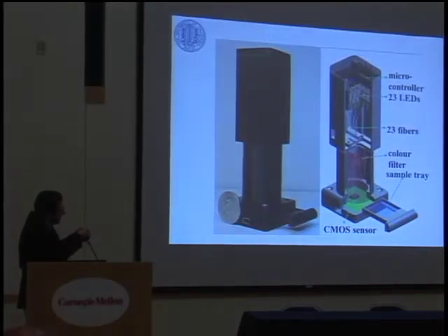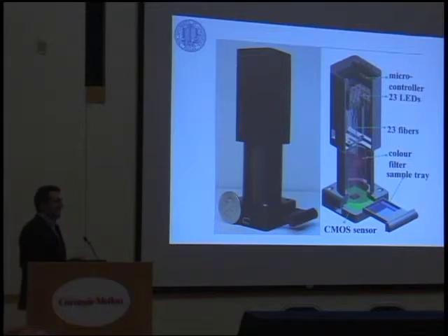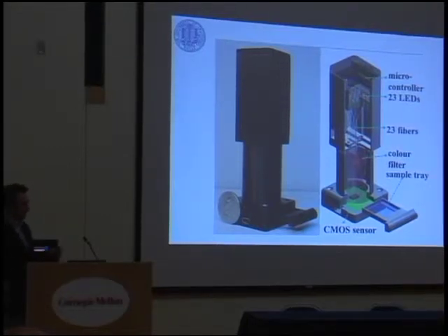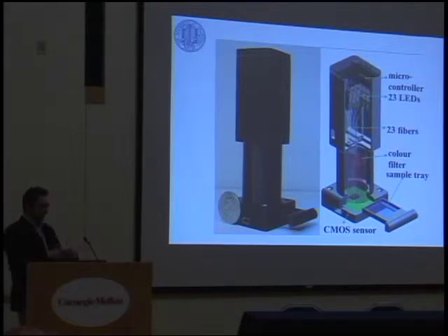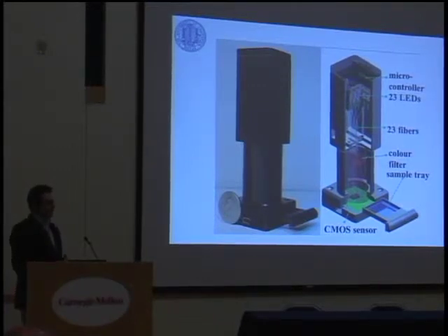The distance between the tip of this fiber and the sample is on the order of a couple of centimeters, let's say 4 centimeters. The distance between the sample and the active area of the CMOS is a millimeter range. That 400-fold reduction in the magnification means that if I move my source by 400 microns, it moves by 1 micron.